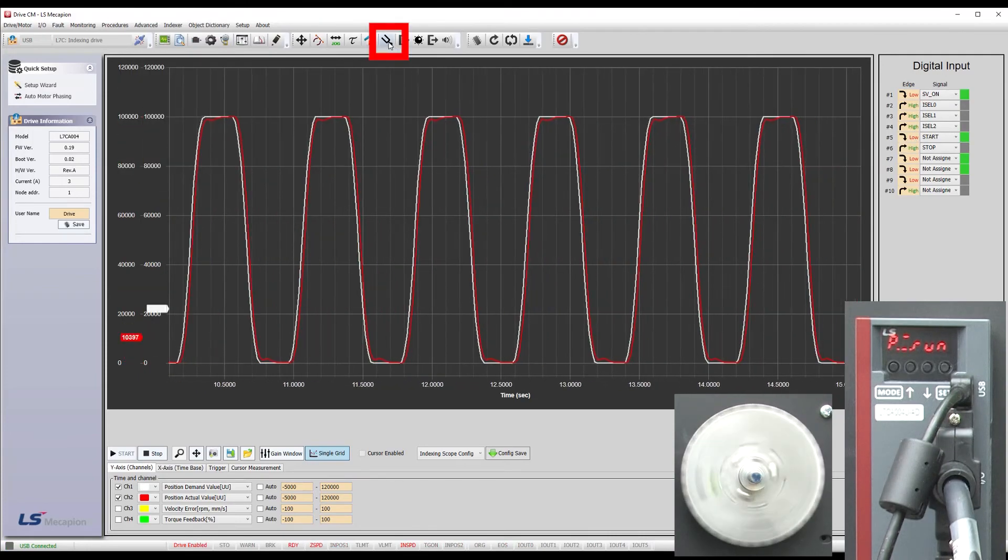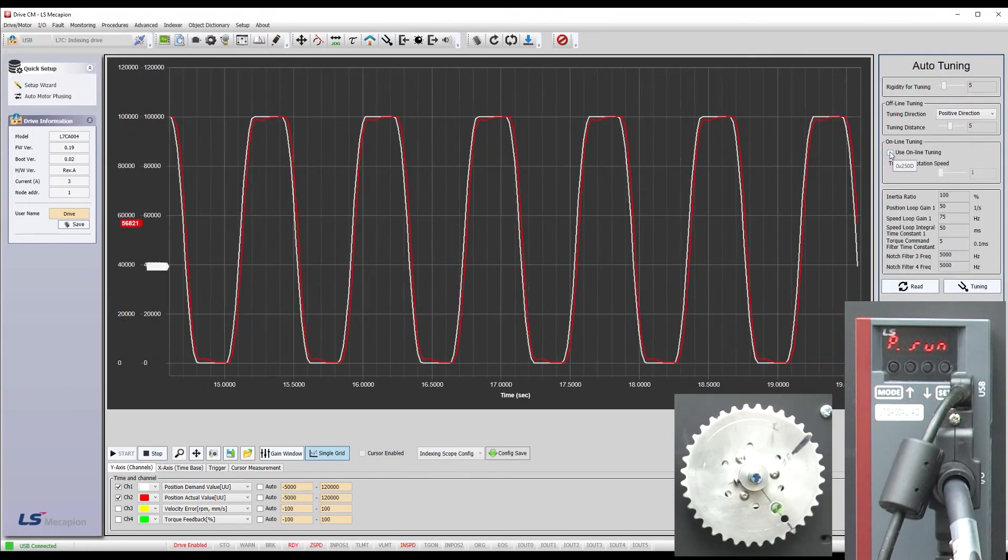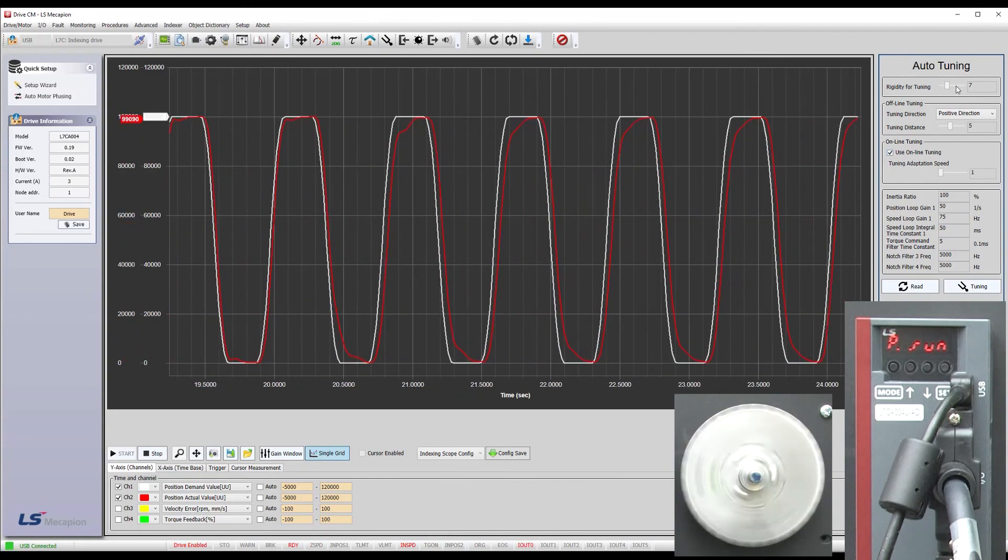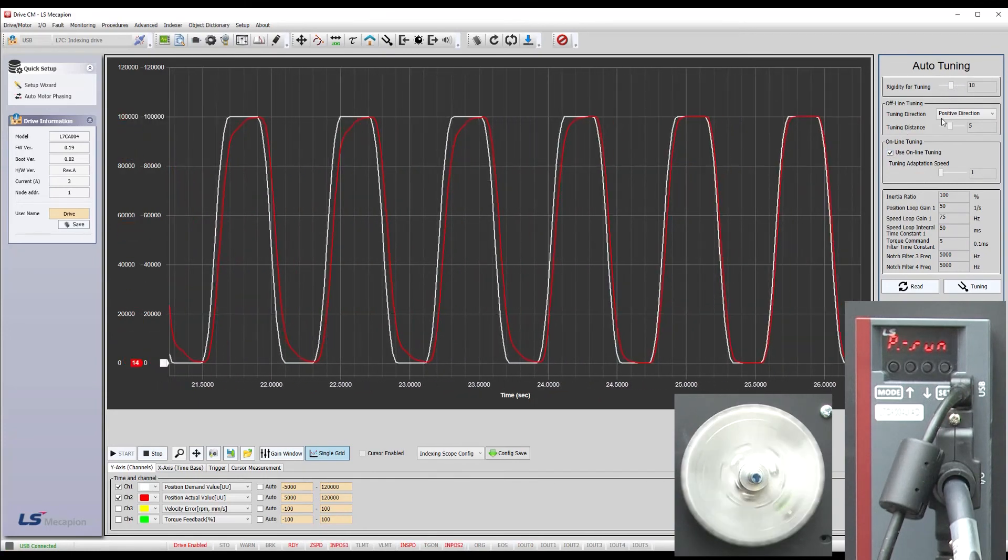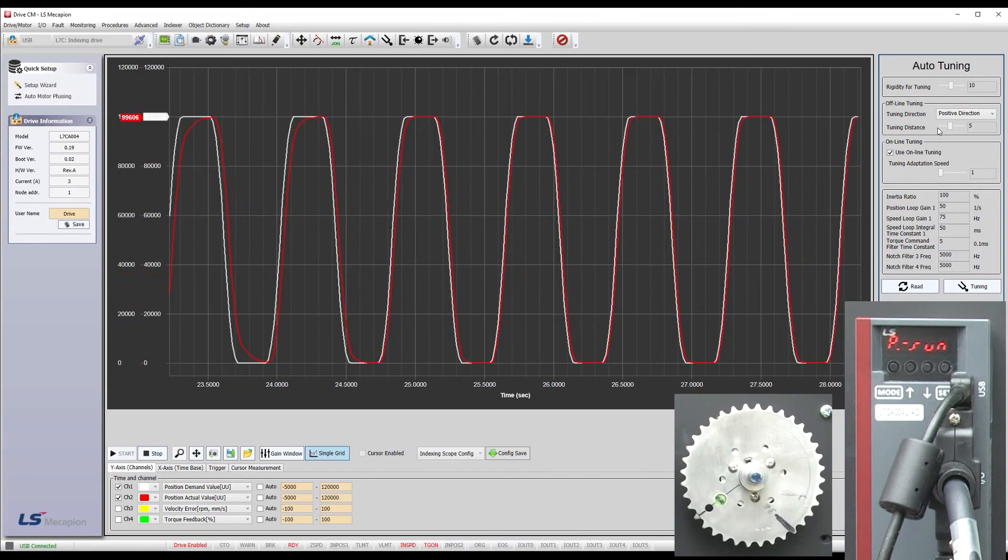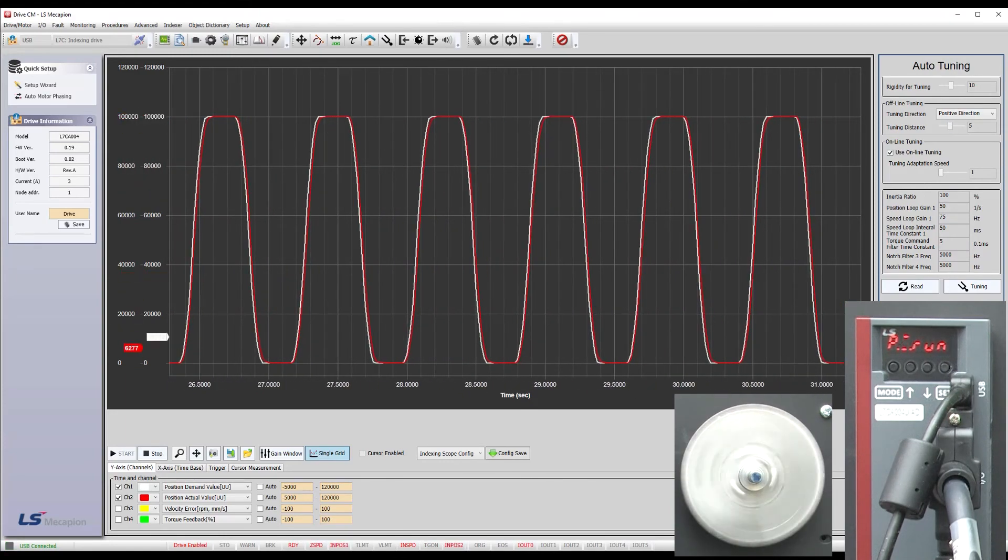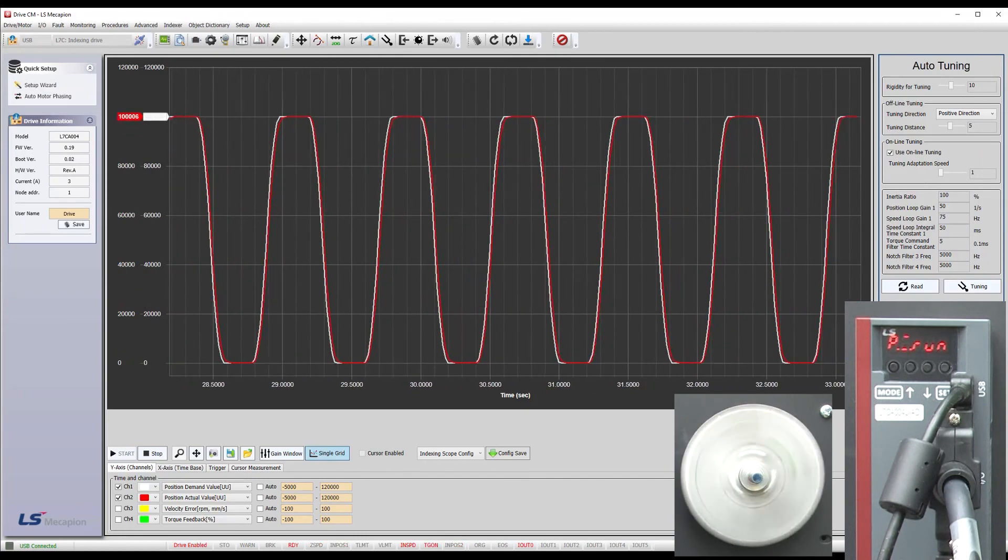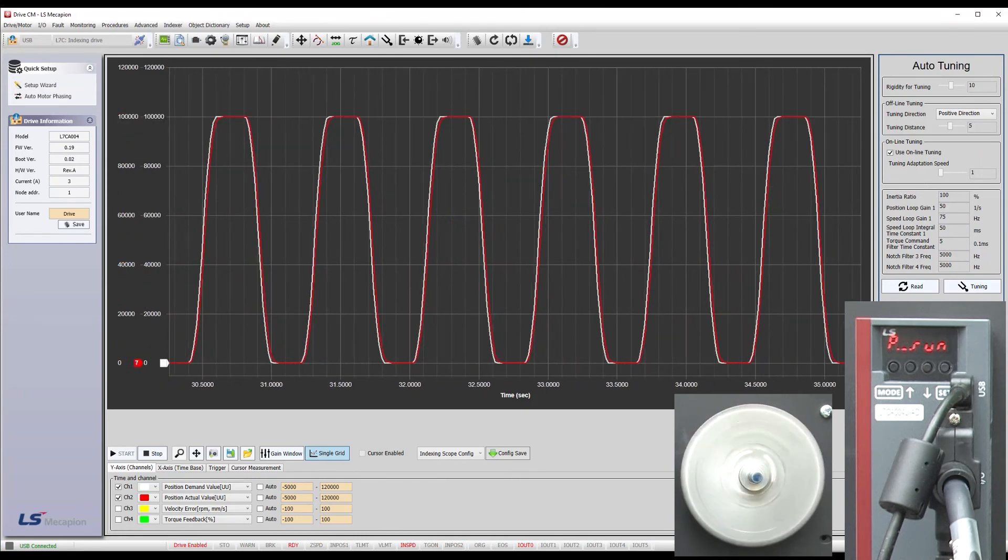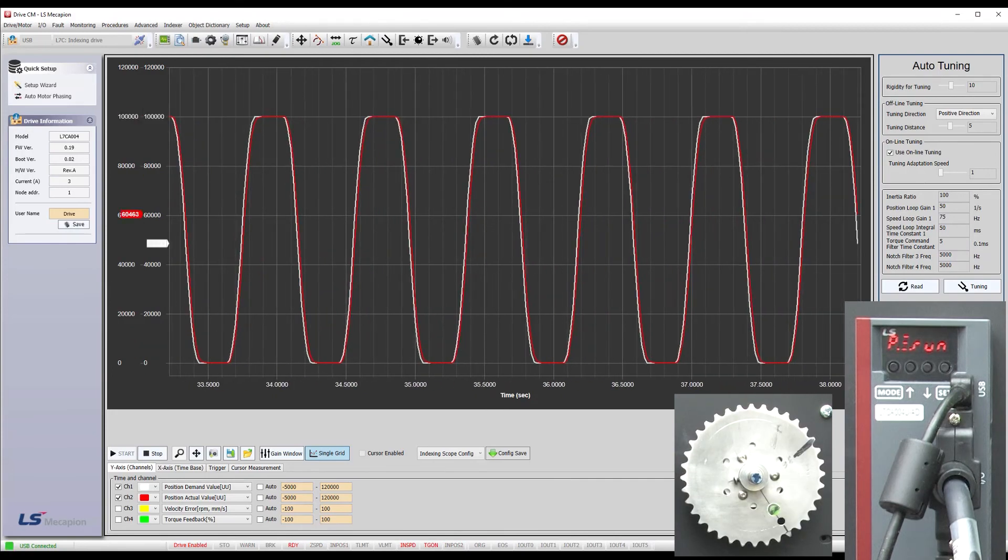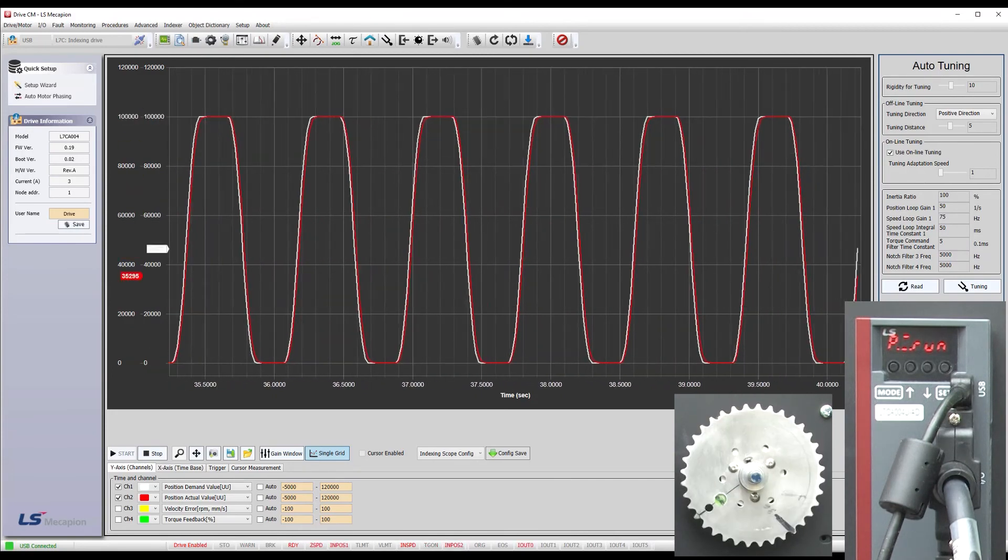And if we go to tuning and click on online tuning, we can adjust the rigidity. But this time, let's stay away from the 12, 13, 14 numbers. Looks like around 10 is all we really need. And that's the key takeaway from all of this. Don't overdo rigidity. The farther you are away from the rigidity that caused the alarm, the more stable your system will be.